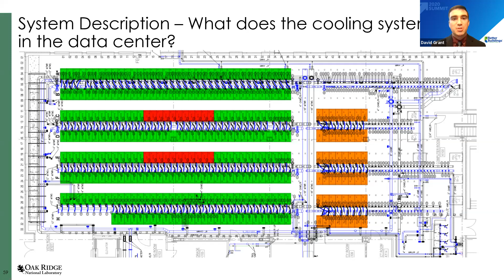This was the data center layout. It's roughly 9,400 square feet. The green represent the 256 compute racks. The red are the switch and management racks. And then the orange are the storage support racks. And you can also see the piping distribution. We basically put the racks in a hot aisle, cold aisle configuration, even though with rear doors, you don't typically have hot aisle, cold aisles. We actually call them inlet aisles or outlet aisles. And we basically put all the water connections for 2 rows down one of the wet aisles. And then the electrical was distributed overhead over the rack. So we avoided any potential for hazards from drips. Next slide, please.